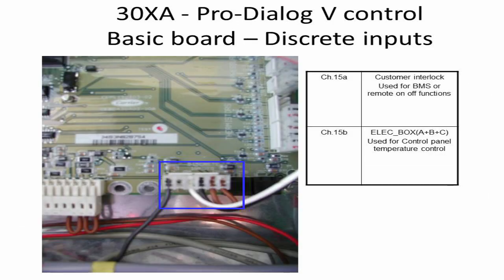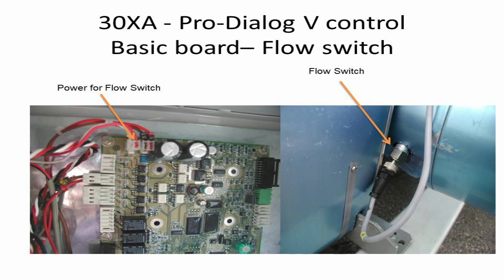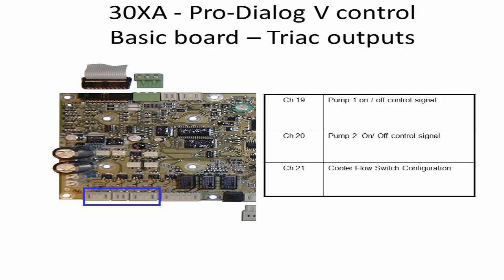Channel 15A is used for BMS connection. Channel 15B is used for the electrical box temperature sensor. The flow switch connection on the basic board is shown using the pointer, along with the physical installed location on the chiller. The table also shows pump control and cooler flow switch configuration with their respective connection channels on the basic board.